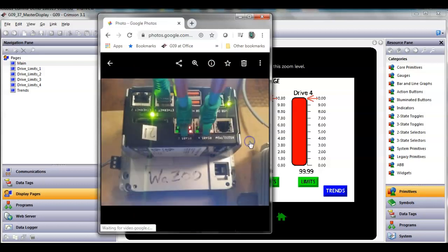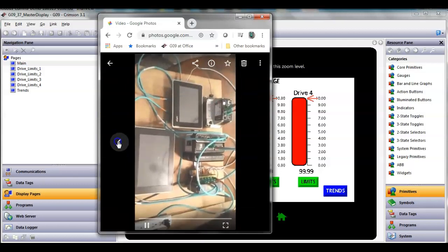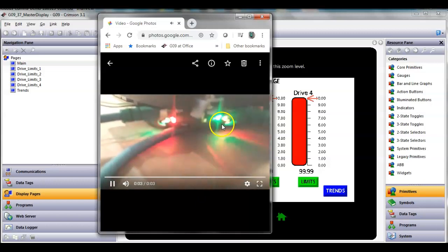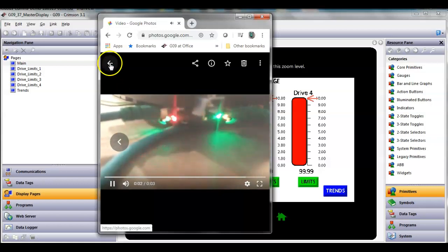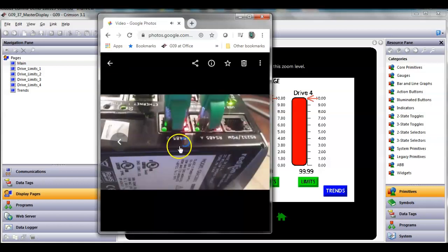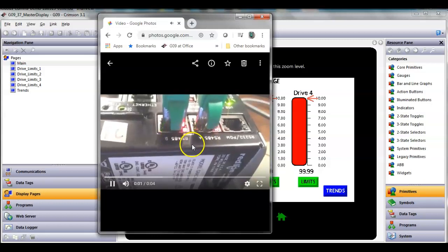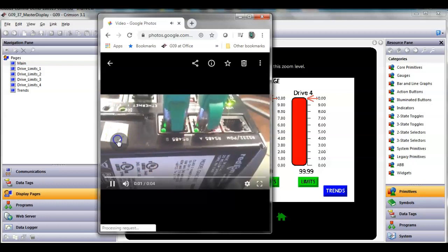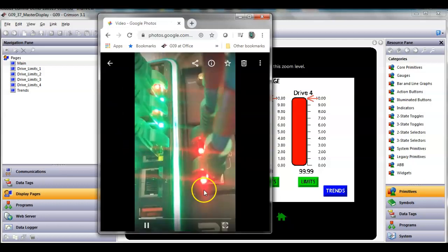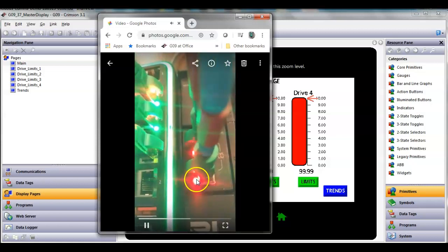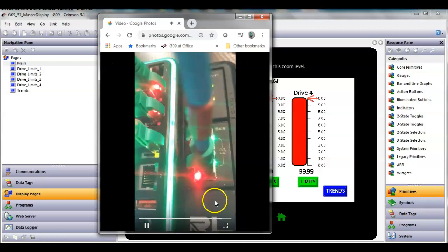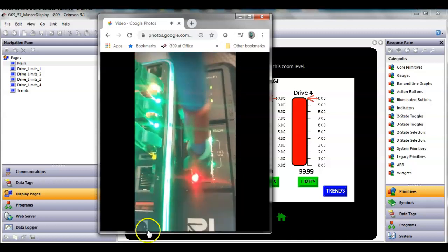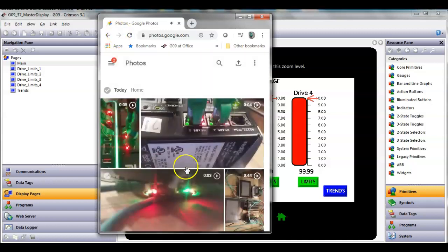Here's what the 485 ports look like on the G07. When you're testing this, you should get red and green blinky blinky. That's what we're seeing right there. And if I go to the other video, I'm going to show you what they look like here at the edge. You can see there, that's good 485 communications, both red and green blinking. And then this is what the LEDs look like on the edge when you got communications.